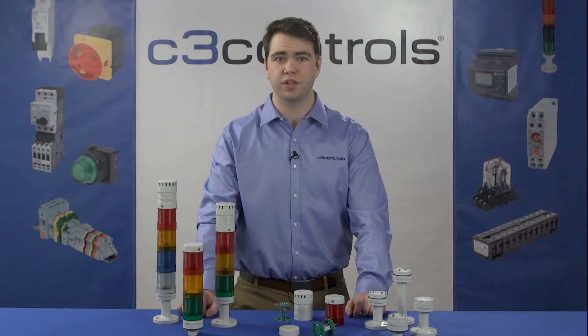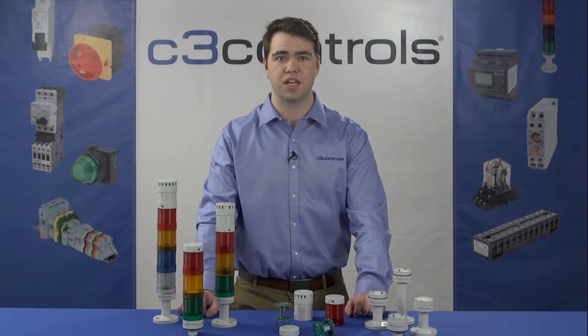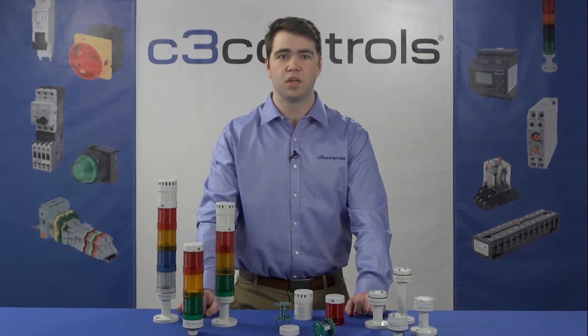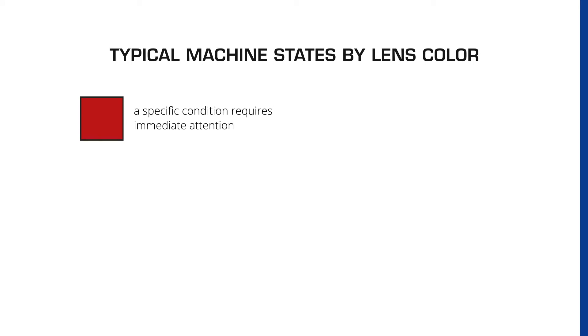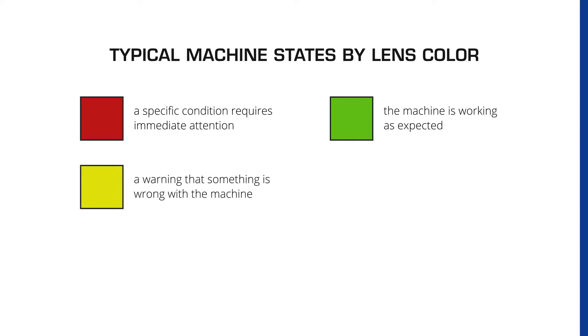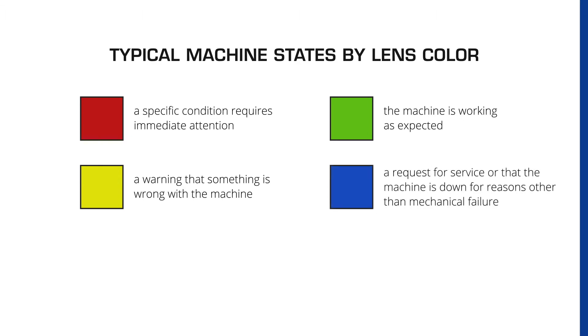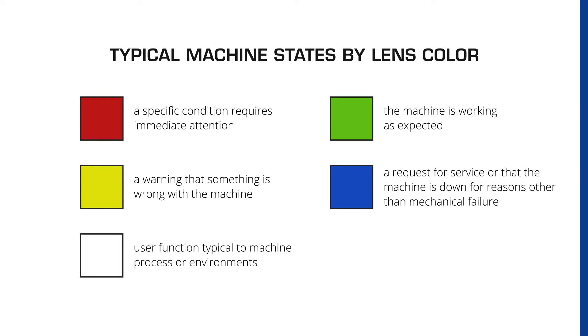Tower lights are equipped with different colored lenses which indicate a typical state of the machine or process environment. Red indicates that a specific condition requires immediate attention. Green indicates that a machine is working as expected. Yellow indicates a warning that something is wrong with the machine. Blue indicates a request for service or that a machine is down for reasons other than mechanical failure. Clear or white indicates user function typical to machines or process environments. These colors are not restricted to these functions, but rather are decided by the system designer in response to machine and operator requirements.